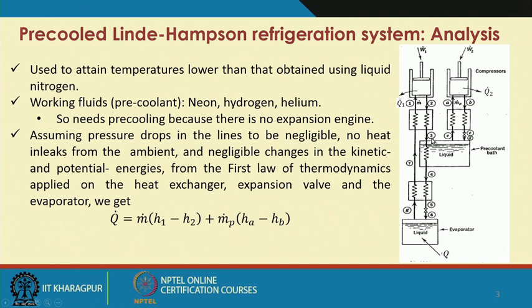Here we are applying further cooling — this cooling is being done by another system, which looks the same as the simple Linde-Hampson. This gas is passing through the liquid reservoir of the auxiliary system. It is further cooled and then taken to another heat exchanger for still more cooling. From point 2 up to the expansion valve, a series of cooling steps are done, ultimately taking it to the expansion valve where it is expanded isenthalpically, giving us a two-phase mixture of liquid and gas.